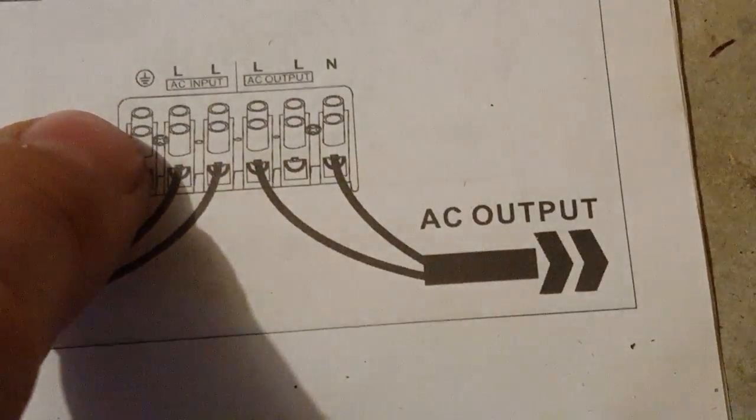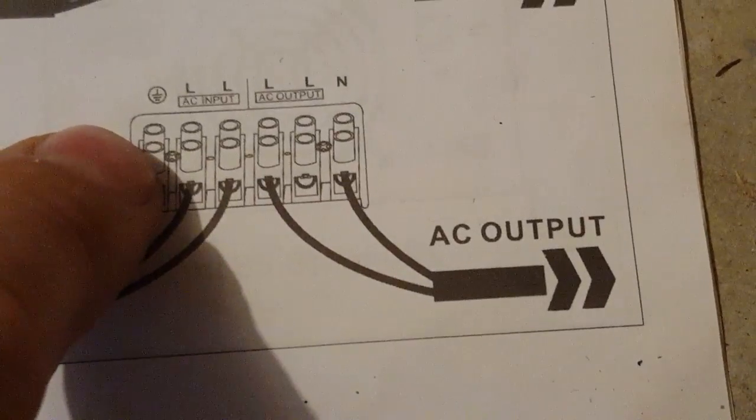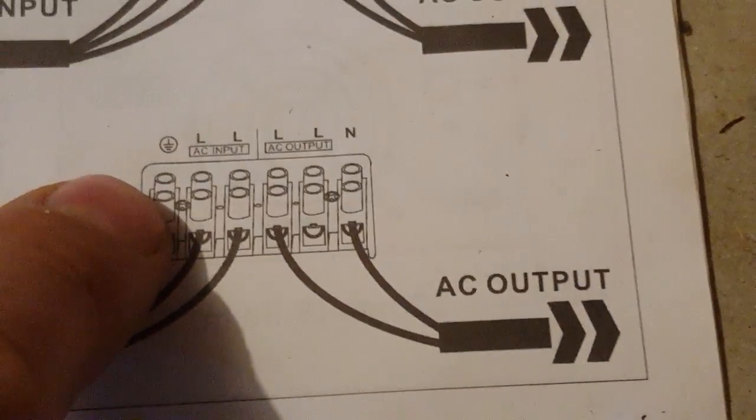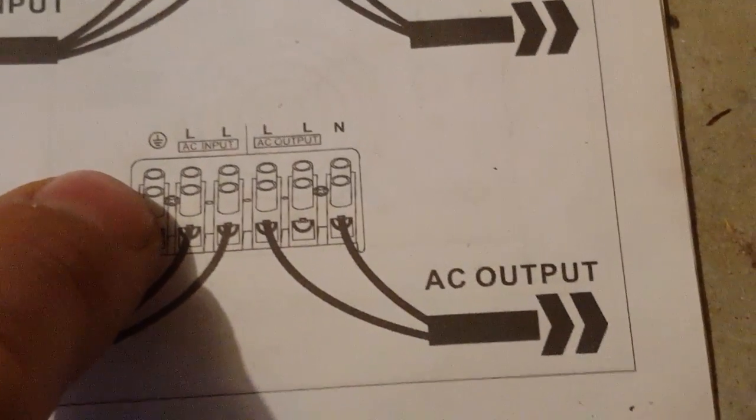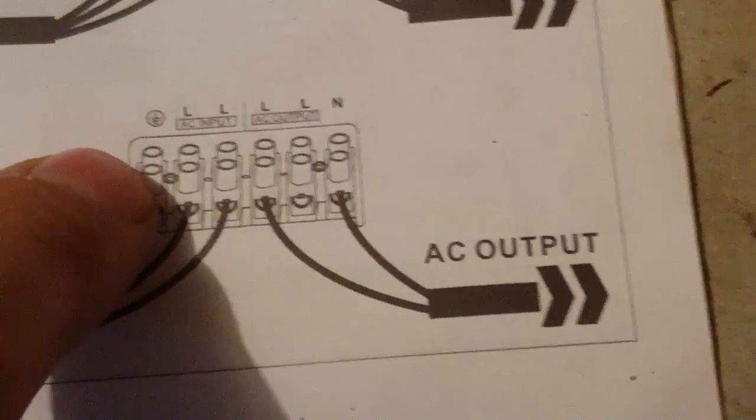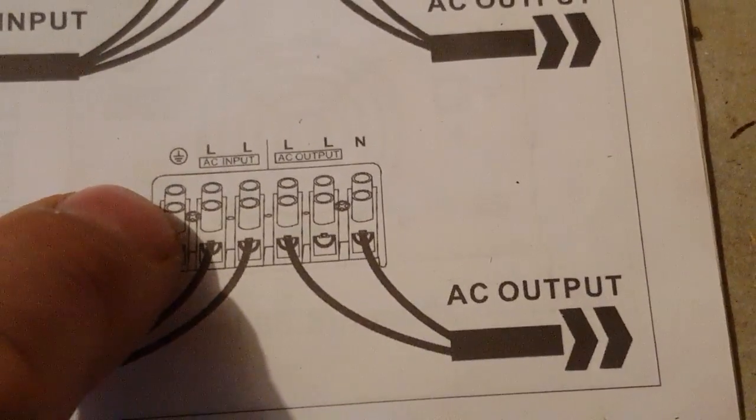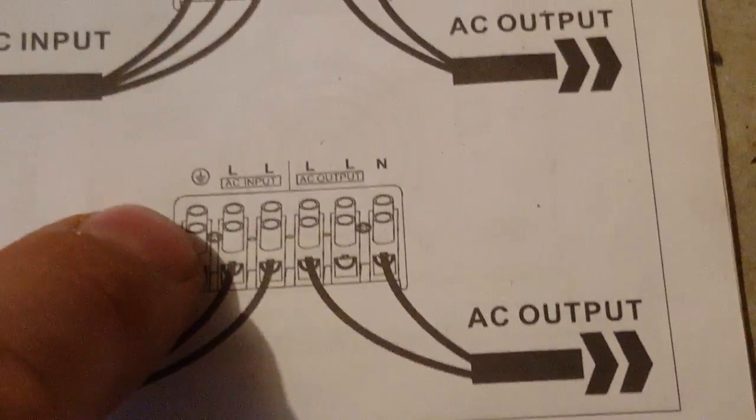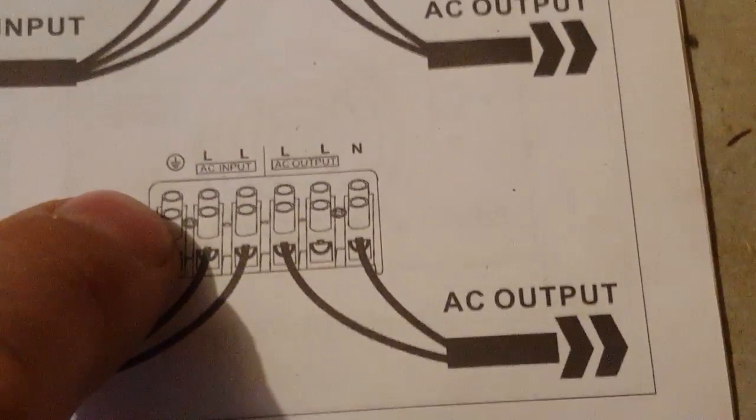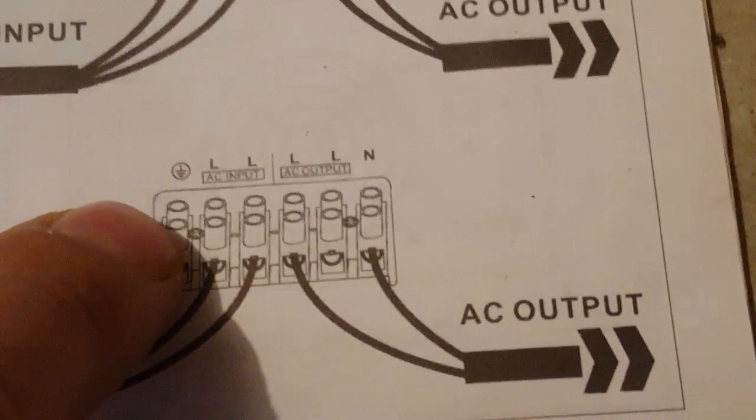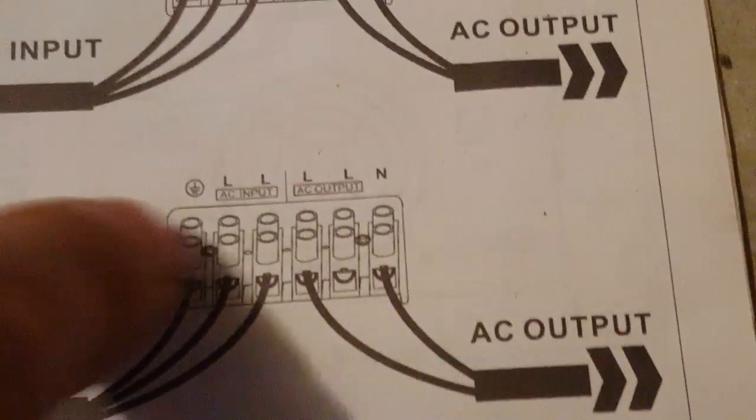Ground, leg one, leg two, leg one, leg two, neutral. This neutral goes to your sub panel. This ground goes outside to a ten foot ground rod that's copper, and you drive it in the ground. You don't leave half of it sticking out because it ain't done yet.